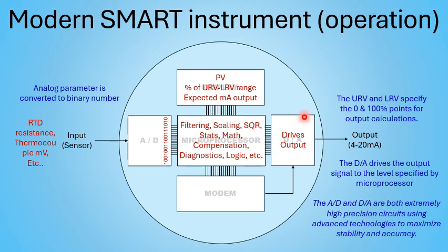A lot of times, I know on the Rosemounts it just says mA, it says milliamps, and people will see that and see 12.0 and say, oh, it's 12.0, we're good to go. You've got to check that 20 milliamps, because that is just telling you that the microprocessor is good on the A to D. If this digital to analog is bad, this signal may not be at 12 milliamps. Even though it says 12.00 right here, it might be 11.5 over at the output. So that's why all of our procedures always say to check the output.